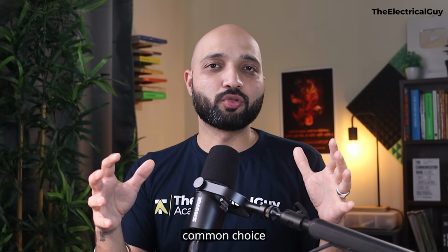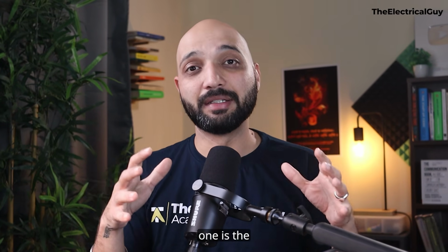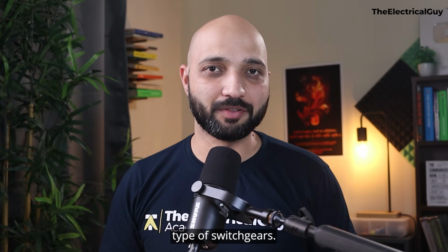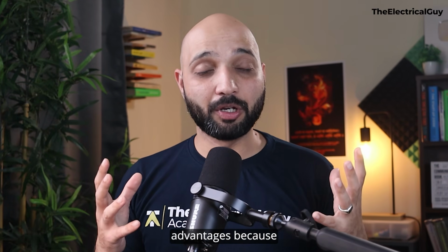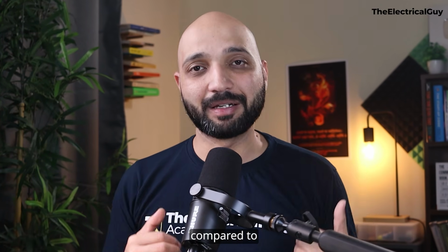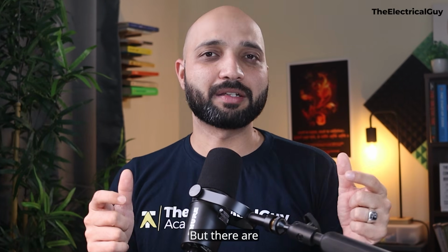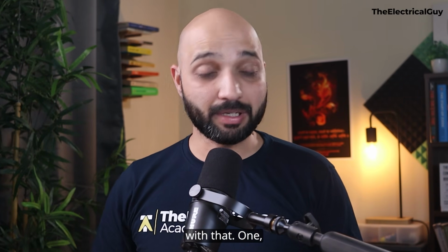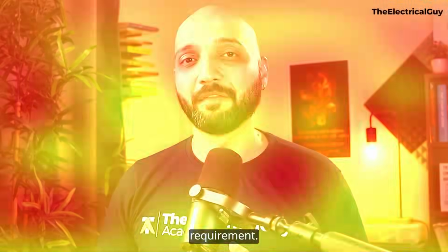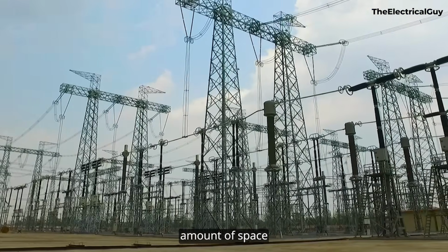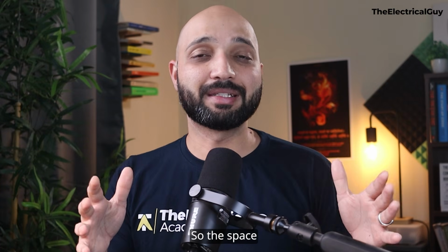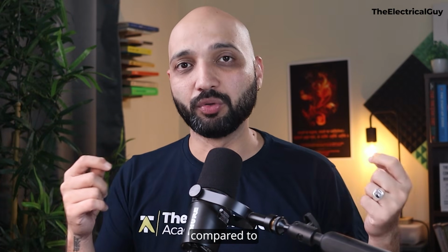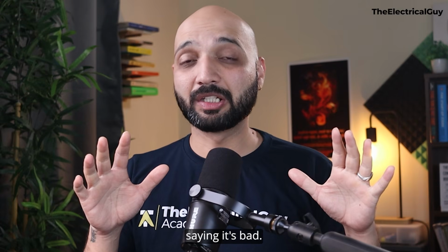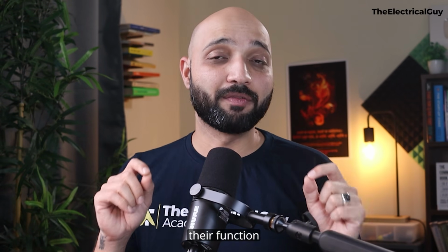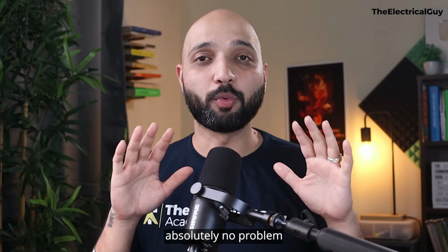Well, the most common choice, just like in AC transmission, is the AIS switchgear, air insulated type of switchgear. The advantage is that the cost would be less compared to the GIS one, but there are some trade-offs. The major one is the space requirement. AIS switchgear needs a huge amount of space because we are using air as the dielectric medium. So the space that you need would be very, very huge compared to the GIS one. But I'm not saying it's bad. They perform their function perfectly well. There is absolutely no problem with that.